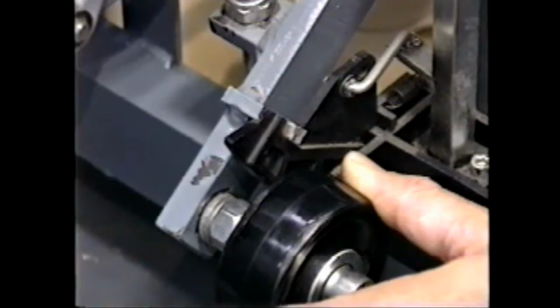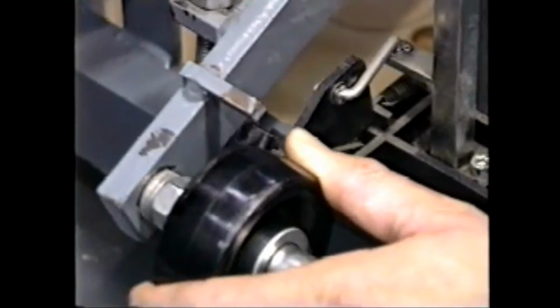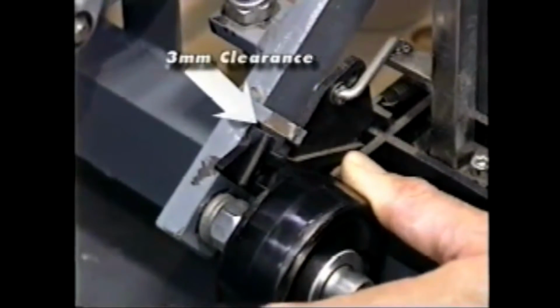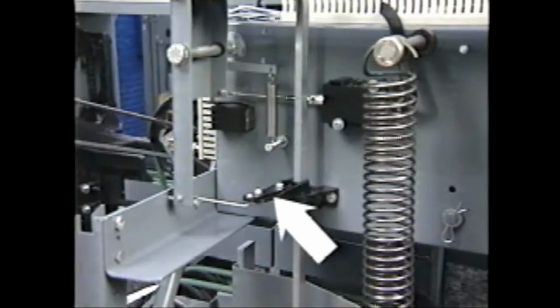Now, manually bottom the plunger in the limiter solenoid, causing the latch hook to pull rearward and away from the latch bow, releasing the swing shafts. If a 3 millimeter clearance is not found, adjust the swing lever.